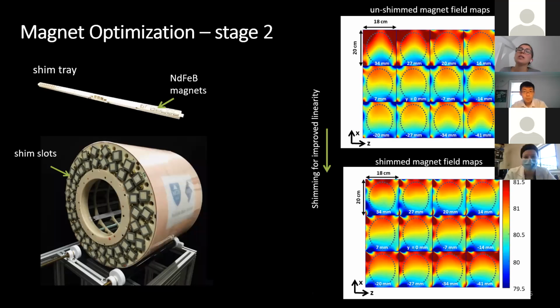We also did a second stage optimization. The linearity of the field that we created wasn't great. You can see on the top right that it was quite non-linear. To account for this, we created shim trays with very small permanent magnets and did another optimization procedure to improve the linearity. On the bottom, you can see that with the addition of the shim magnets, we still have a non-linear encoding field, but the linearity is improved.